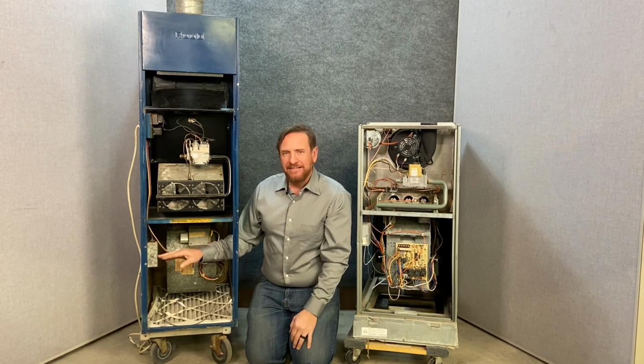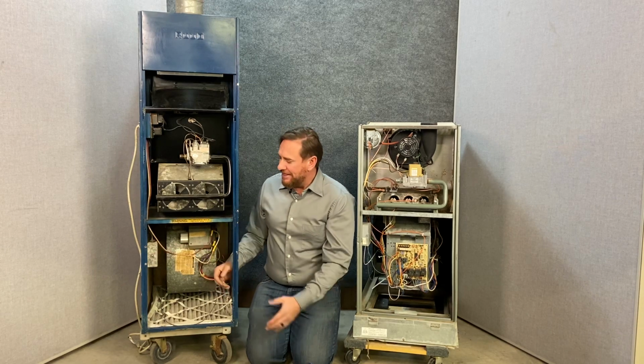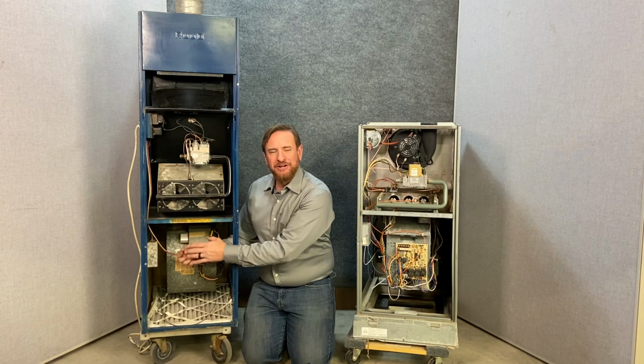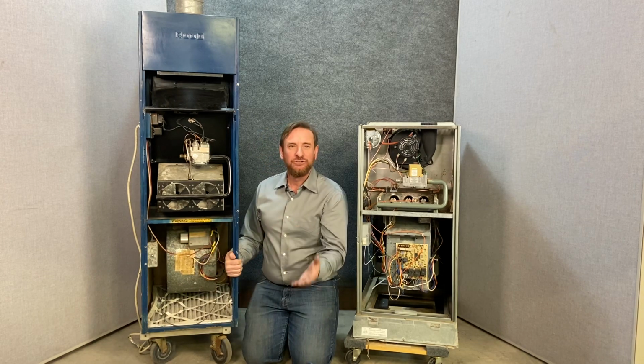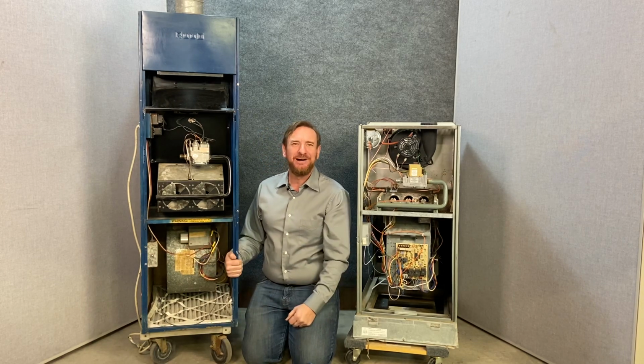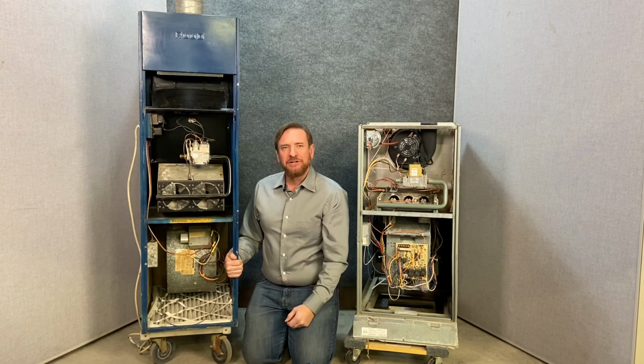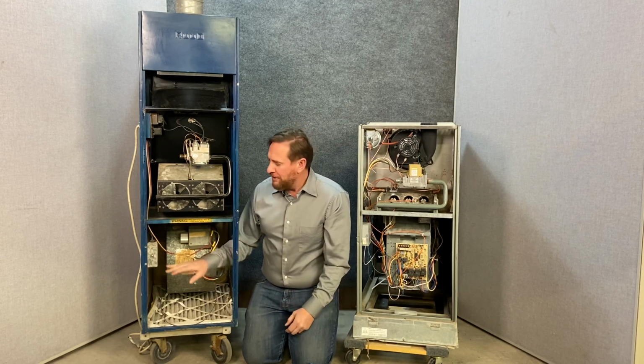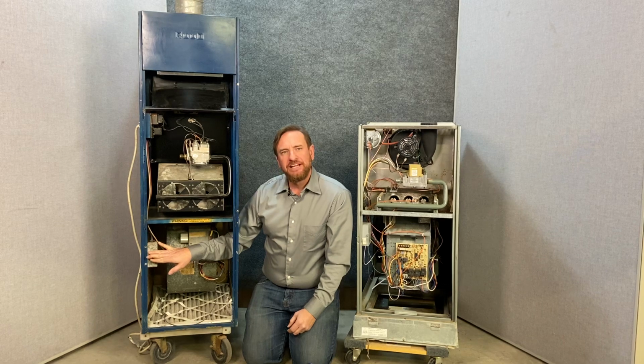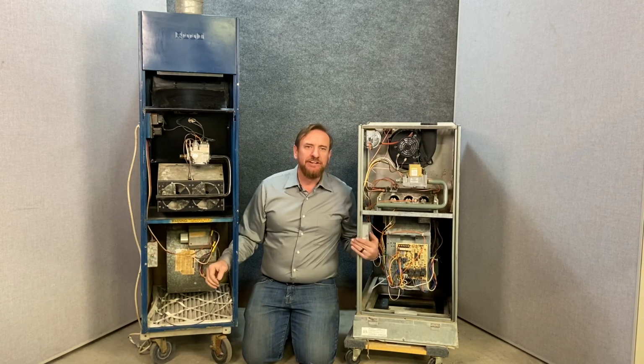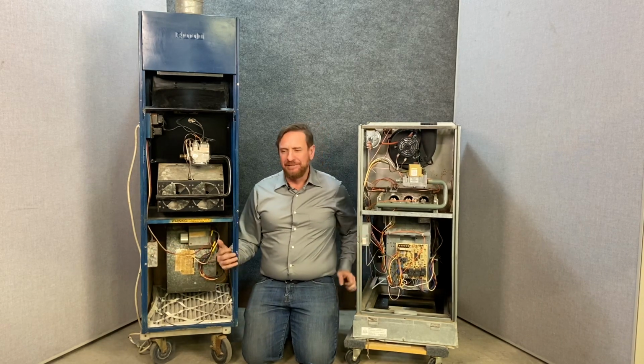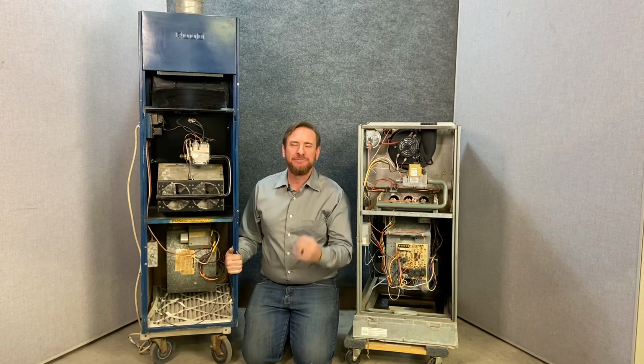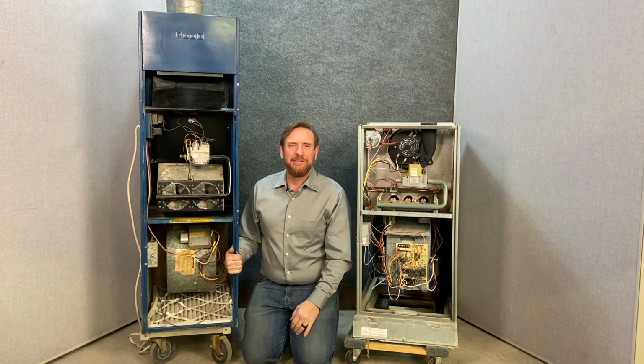What I use is a magnet glued to a 90-degree L. That way I cannot put the door back on without taking that magnet off, and that's a tool, and I don't ever want to leave a tool behind. So there's many out there that are already pre-made. You can make your own, but some kind of a magnet system that holds that switch in on these different furnaces, so you don't have to worry about taping it. Please, it's a bad habit to tape it, just because if you forget, that could be a liability issue.